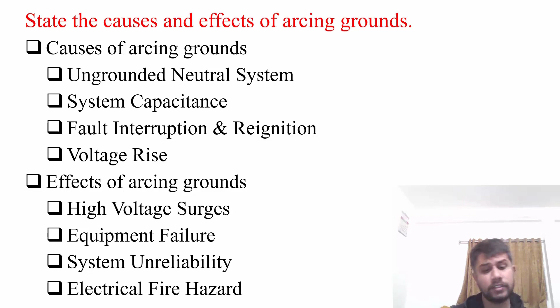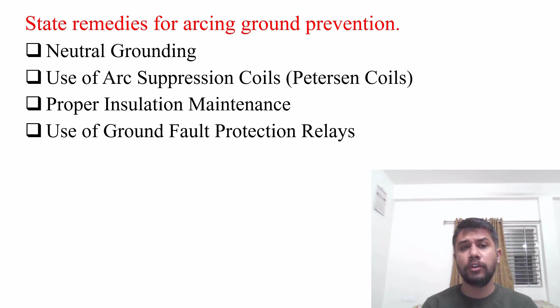So arcing ground phenomenon occurs only due to the floating neutrals or isolated system. So in this case, first of all, use neutral grounding method. Use of arc suppression coils or Petersen coils. Proper insulation maintenance and use of ground fault protection relay. So these are some remedies for preventing arcing ground phenomenon. Explain over voltage produced due to resonance phenomena.